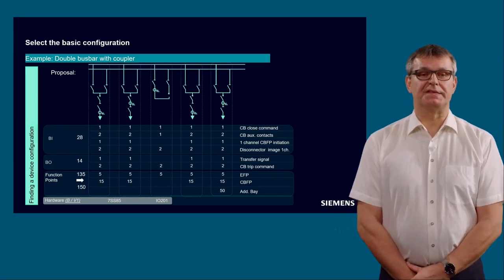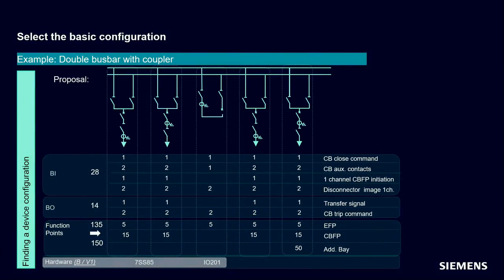So you can see here with hardware variant version 1, we can more or less cover the 3 feeders and the 1 coupler. And to have enough binary inputs and enough binary outputs also for the missing 2 feeders on the right, we extend the configuration with 2 IO201. Then we have a configuration of 5 measuring points, 31 binary inputs, and 25 binary outputs, which is absolutely sufficient for this small double busbar.